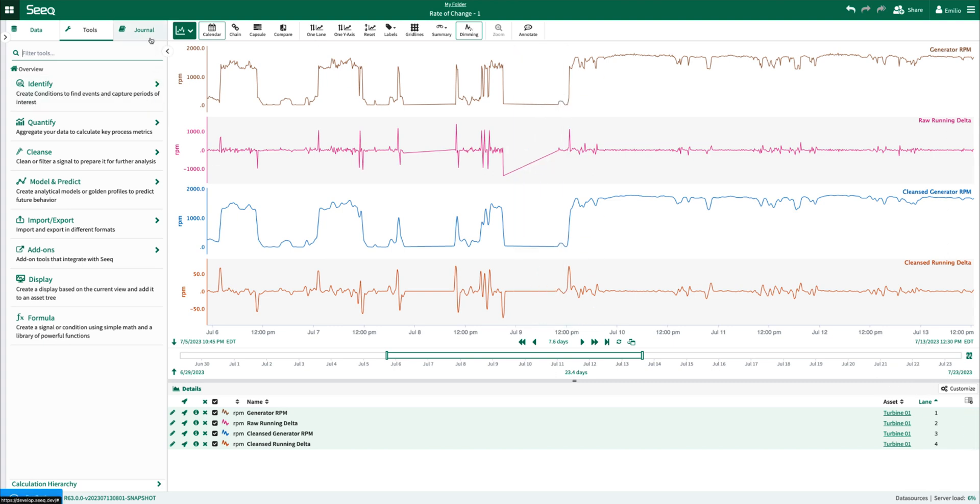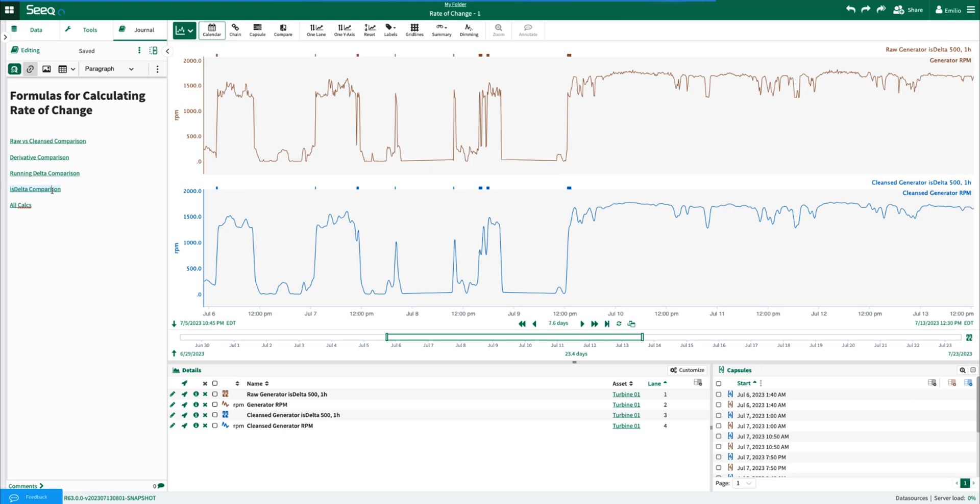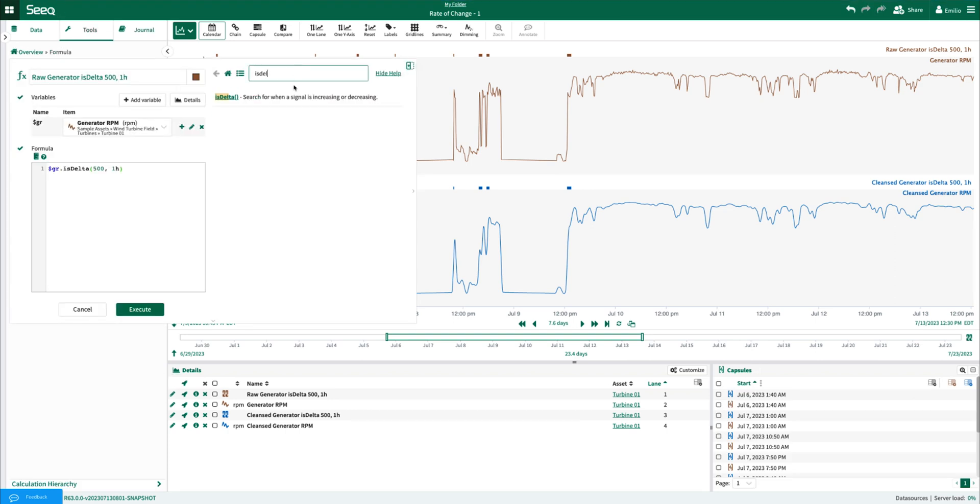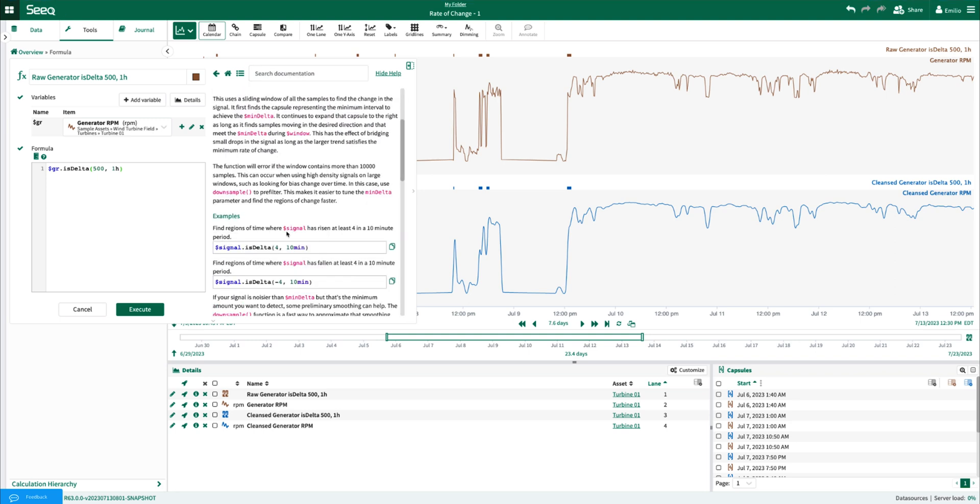The next function is a new function that Seeq introduced as of version 61 called ISDELTA. ISDELTA is meant to identify when a signal is increasing or decreasing, and you can see the way it's used is to provide a magnitude of increasing or decreasing and a rolling time range in which that magnitude must be met in order for a capsule to be produced in the condition.